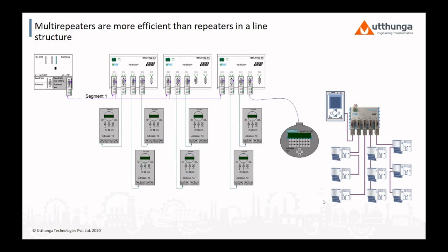Earlier you understood that segmenting with a repeater is necessary, because if the cable length exceeds the limit for the speed and baud rate of your network. The same thing: a person is using some baud rate, such as 12 Mbps, but here he is using a 200 meter cable in a single line, so maybe the repeater is required. It also eliminates impedance reflections, that is why the repeater is required, and for the regeneration of the signal in amplitude and in time, you need the repeater.